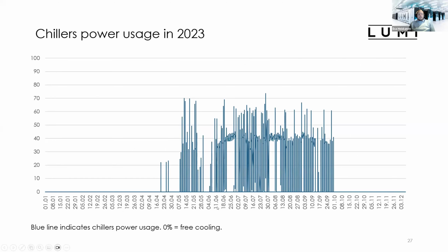So this graph quickly shows the chillers' power usage. As you can see, we are able to operate completely in free cooling until about half of April, and then again from the beginning of October. We are completely in free cooling, and there is only one very short period in the summertime when at night times we also need to use the mechanical cooling. So during most of the summer we are also able to operate free cooling at night time with the room cooling.